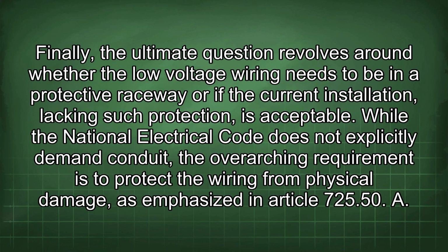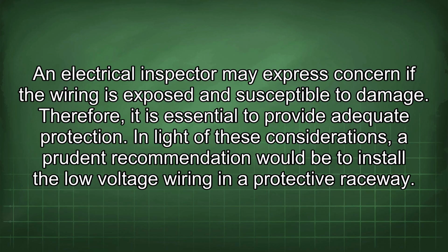Finally, the ultimate question revolves around whether the low-voltage wiring needs to be in a protective raceway or if the current installation, lacking such protection, is acceptable. While the National Electrical Code does not explicitly demand conduit, the overarching requirement is to protect the wiring from physical damage, as emphasized in Article 725.50. An electrical inspector may express concern if the wiring is exposed and susceptible to damage. Therefore, it is essential to provide adequate protection.